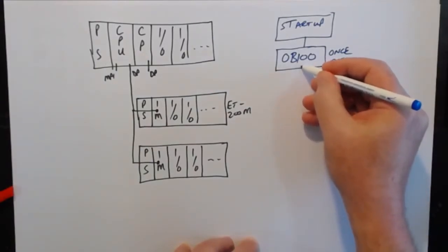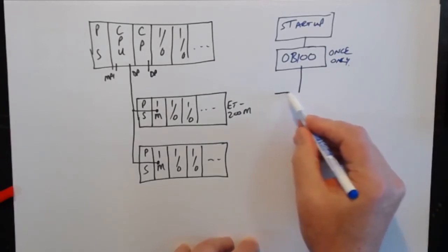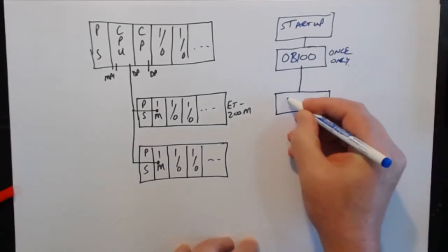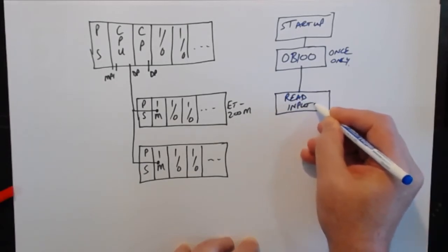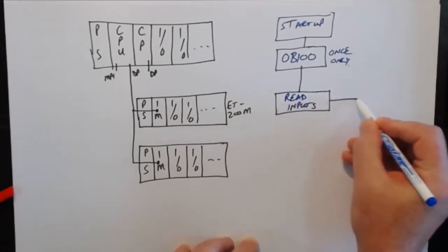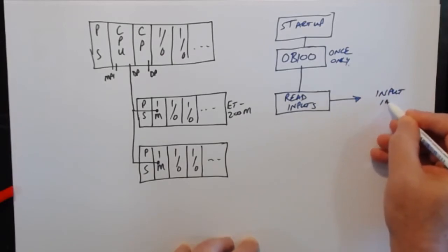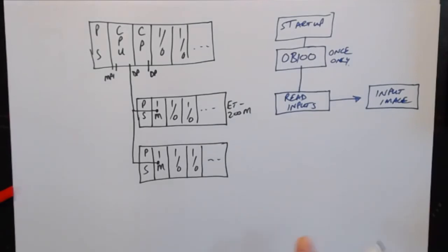After OB100 is called, it runs into the main loop. The first thing that happens, all the inputs are read from the hardware and put into memory in what they call an input image. And your program will use information from the input image rather than directly from the inputs.